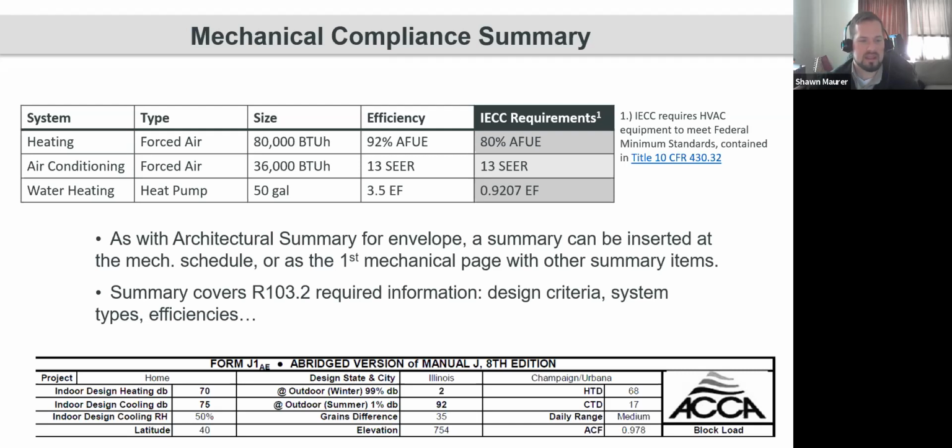But it's very important that you're not using rule of thumb calculations that have been typically used in the past to try to size equipment. Because homes are so much more airtight now and more efficient, insulation levels have gone up significantly. And the distribution of loads in the house between the envelope and internal loads like electronic devices and people have changed significantly. And so these Manual J calculations help ensure that you're accounting for that shift in the load balance and properly sizing the equipment to handle those different loads.